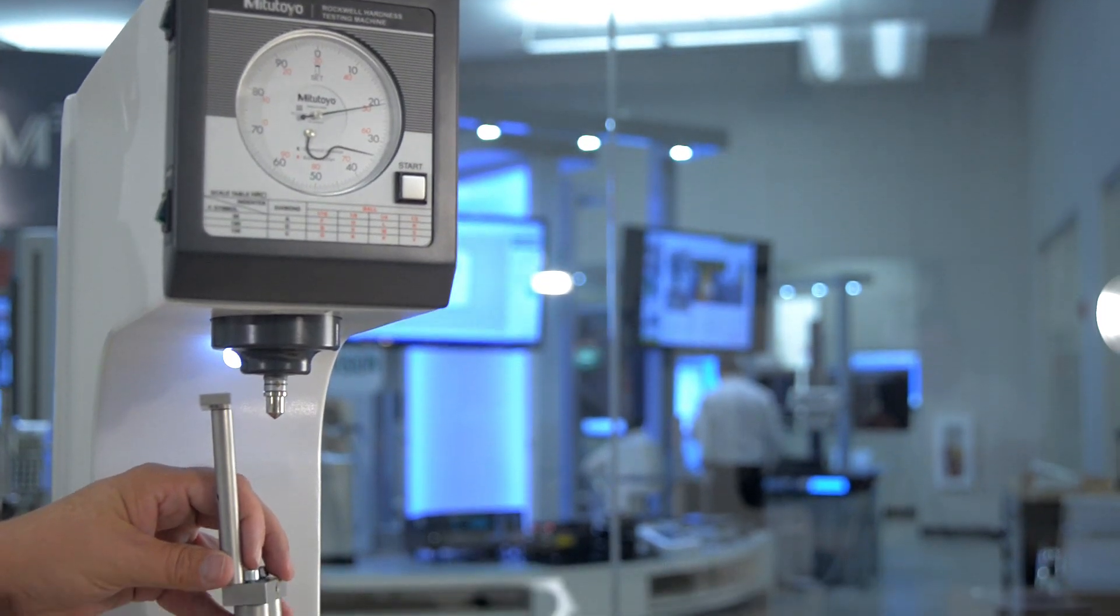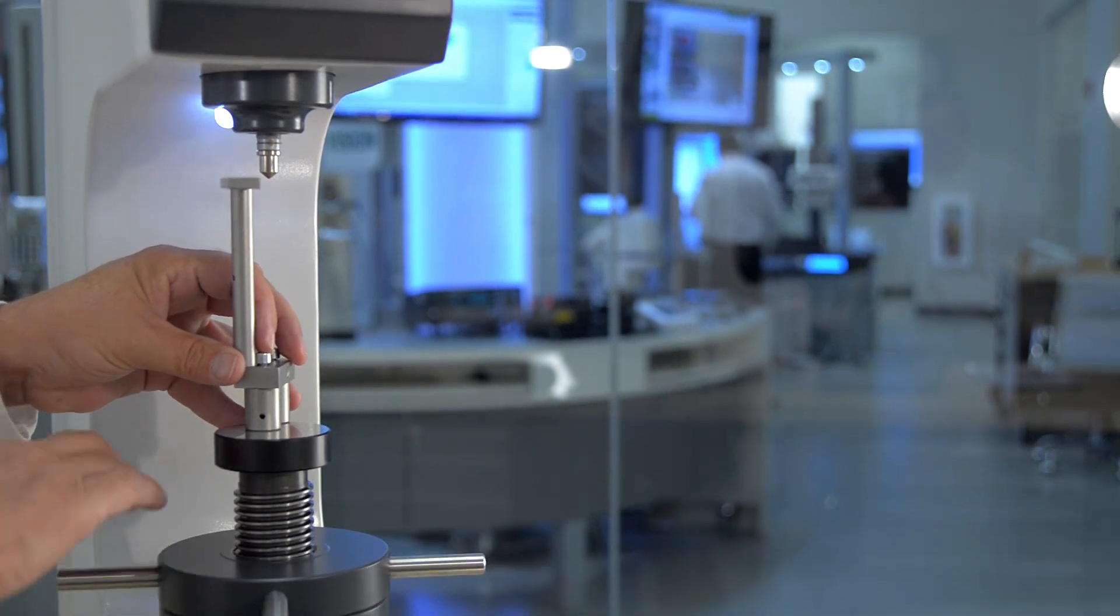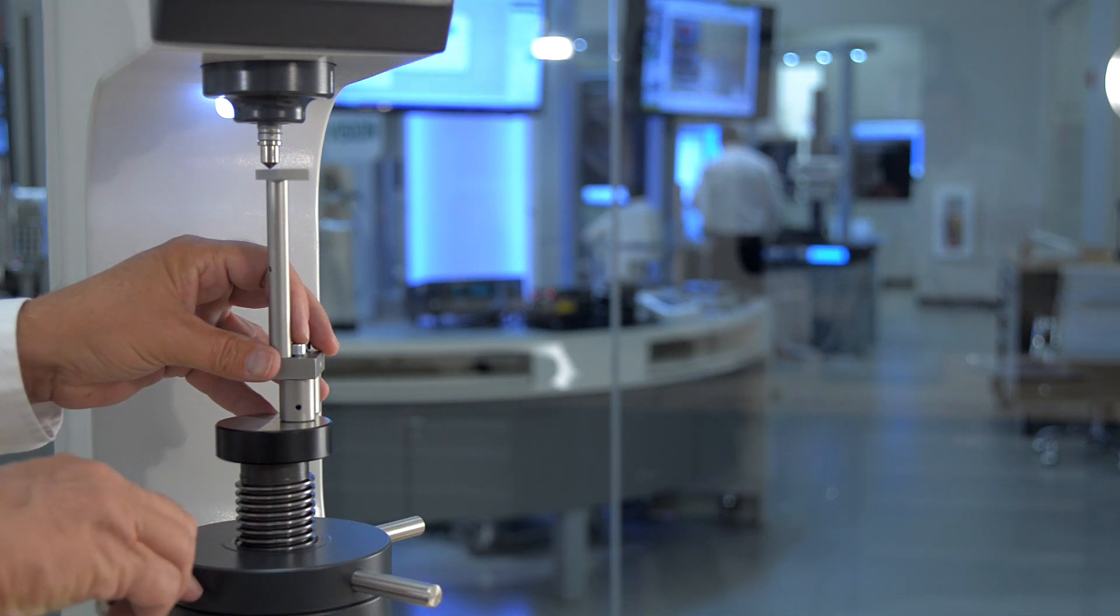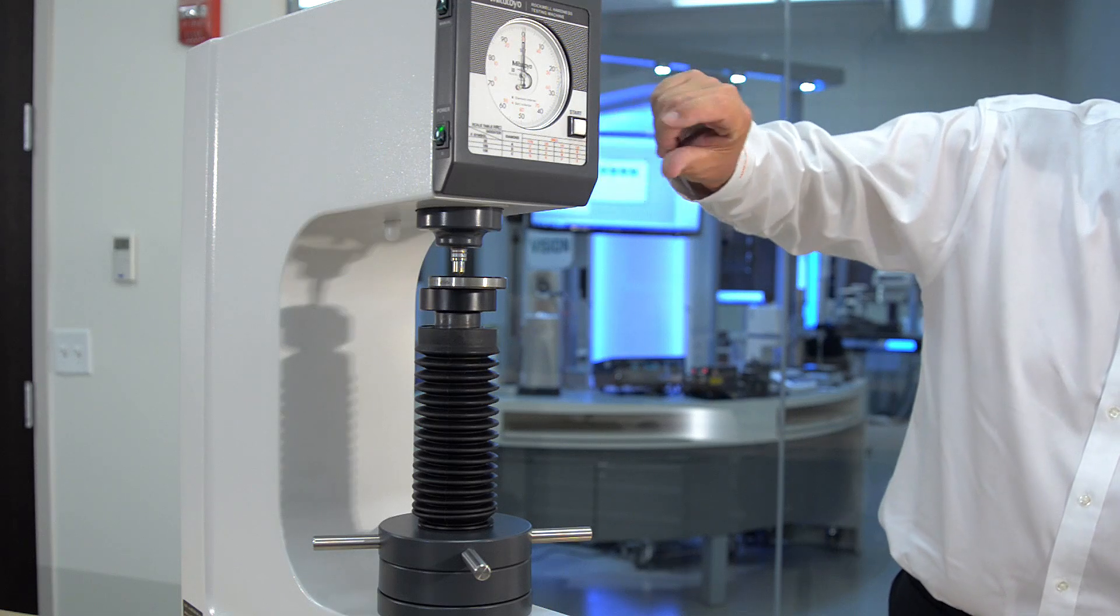Let's start with the Dial-Type HR-210. It was designed to be an economical tester for those requiring an accurate Rockwell test at an economical price.